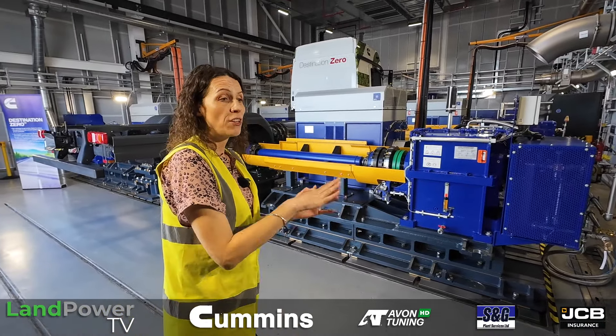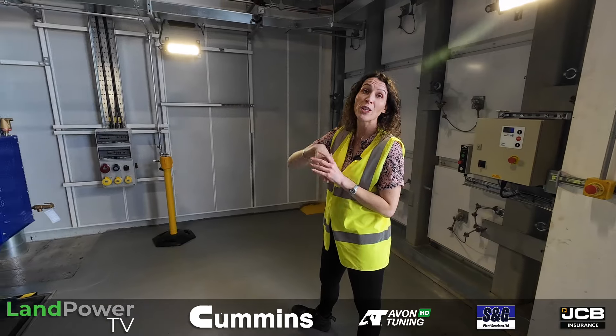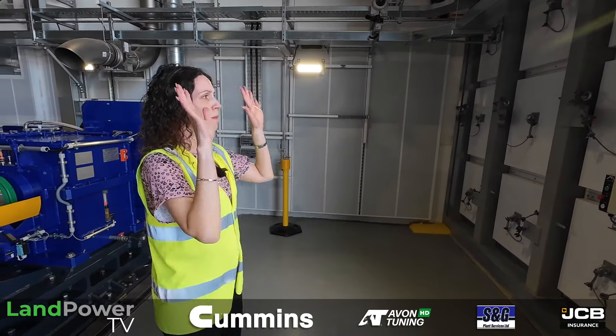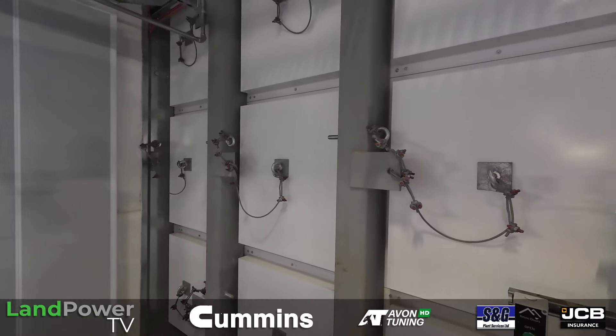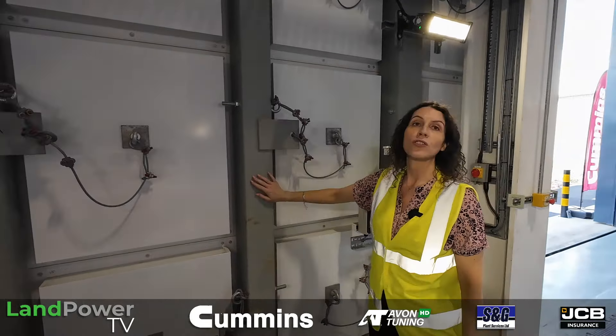The blast wall is designed to the highest grade, meaning there would be superficial damage but it would survive the explosion and stay standing — whereas lower-grade concrete walls could withstand an explosion but would break and need replacing. Think of the control room as a bunker — you can see the thickness of the blast-rated doors when you go in. At the front face of the building there are also vented panels, which channel any pressure from an explosion out through the front of the building. These panels are tethered to the structure of the building.